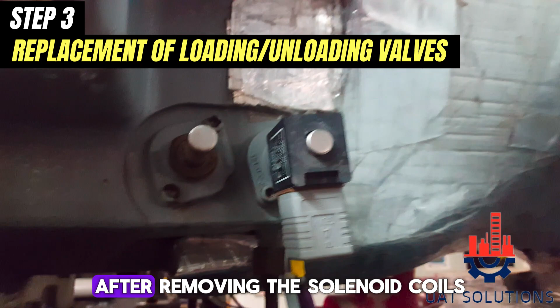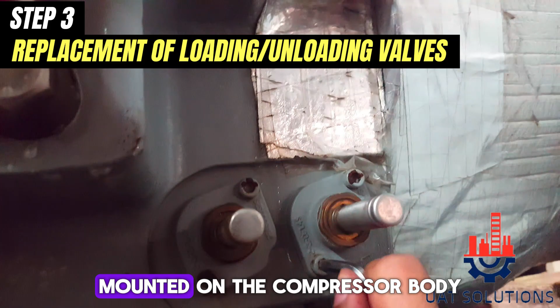As seen, the suction pressure is in minus now, which means all the refrigerant from the compressor side has been moved to the condenser, and now we can proceed to loosen the compressor loaders. After removing the solenoid coils, use the L key to loosen the two screws holding the loader and unloader valves mounted on the compressor body, and replace them with the new valves.